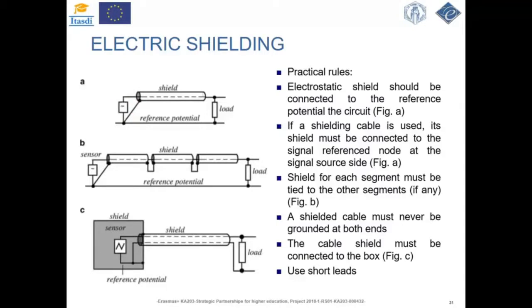If the shield is split into sections, which can occur, for example, if we use a connector in connecting the data acquisition systems, the shield for each segment must also be tied to the other segments and to the signal reference node. This is shown on figure B. So these are different segments, and we connect all the segments to the grounding. Also, a shield must be grounded only at one point, and if possible, we ground it next to the sensor. Moreover, a shielded cable must never be grounded at both ends, because then we will have ground loops. If a sensor is enclosed in a shielded box and data is transmitted through the shielded cable, the cable shield must be connected to that box. This is also shown here in figure C.